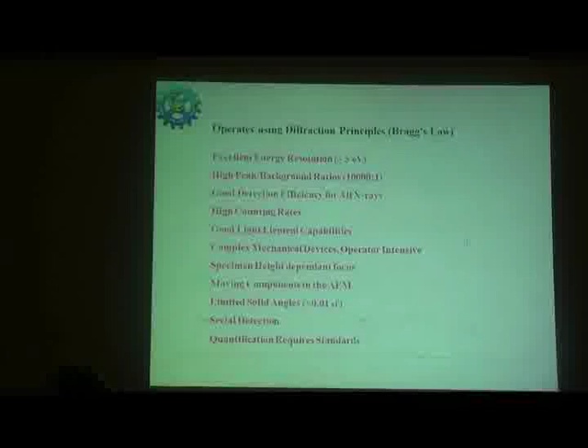Detection efficiency depends upon the X-ray energy, and the X-ray energy comes from the elements. Suppose you have lighter elements like oxygen, lithium or hydrogen; their X-ray energies are very, very small. In that case, EDS will not be able to detect those elements whose X-ray energies are very small. X-ray energy comes from the internal transitions of the electrons, how you get K alpha, K beta. Those energies are what is going to be detected by the EDS.